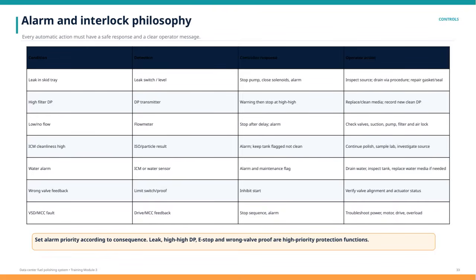Let's go through the alarm and interlock philosophy that guides our system control. The fundamental principle here is that every automatic action taken by the system must ensure safety first and provide a clear, understandable message to the operator.